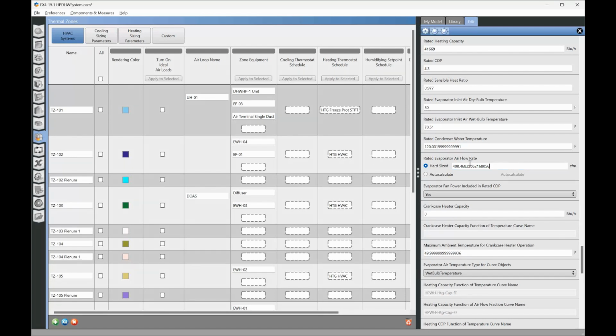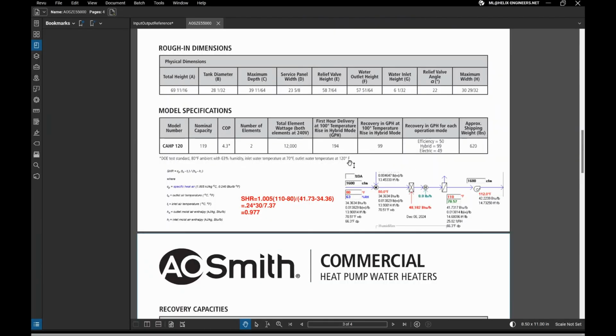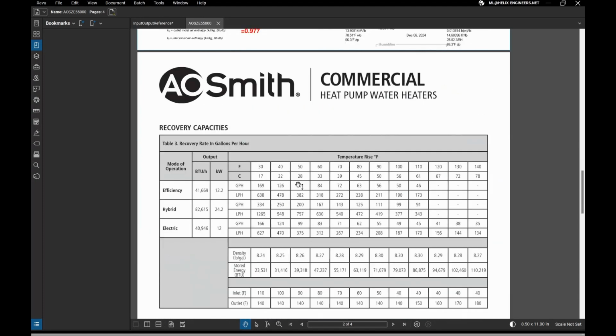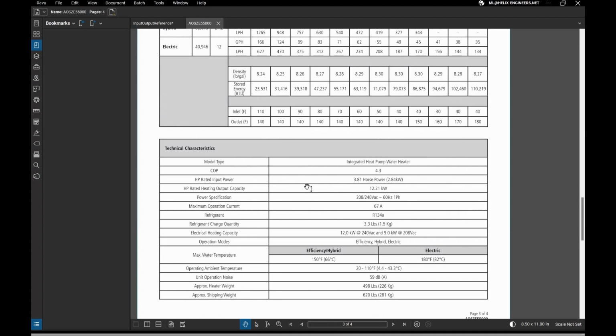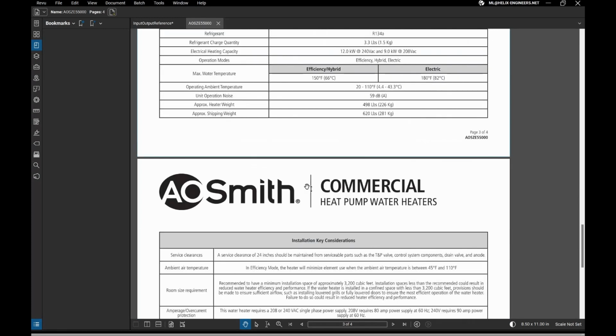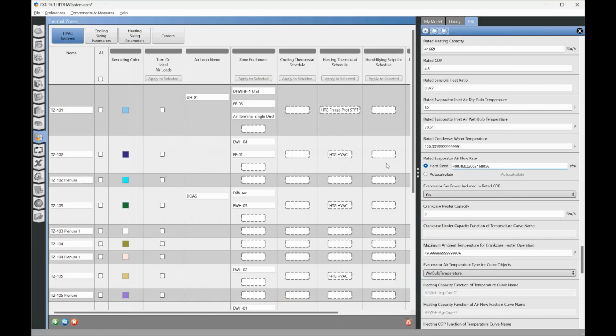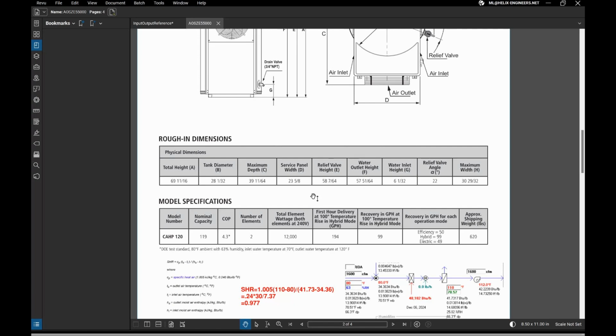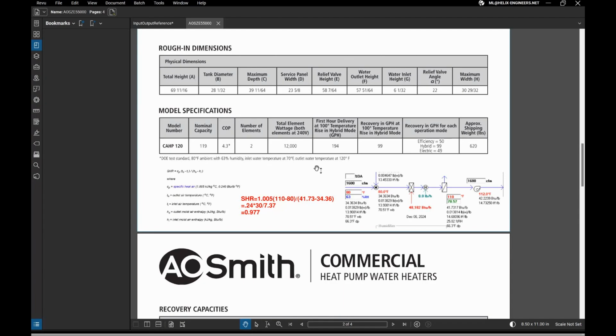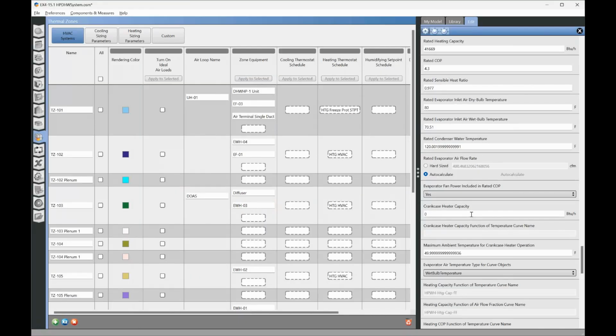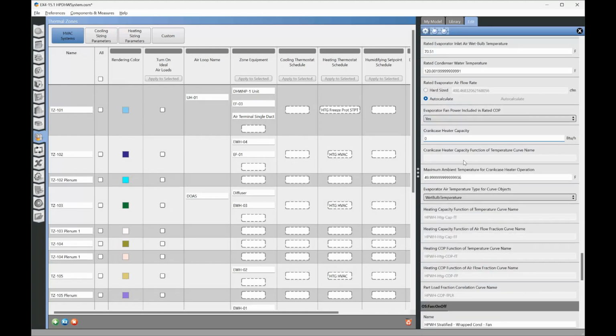And then we've got a rated evaporator airflow rate. This is unlikely to be found on the manufacturer's literature. Yeah, I doubt it's on here. So what we could do is just put auto calculate on there. Evaporator fan power included in the rated coefficient of performance. Most likely it is. I believe the DOE ratings require that evaporator fan to be included. Crankcase heater capacity. Usually these are located indoors, so crankcase heaters are not necessary. So we'll put that at 0. Maximum ambient temperature for crankcase heater operation. We don't have a crankcase heater, so we can ignore that.